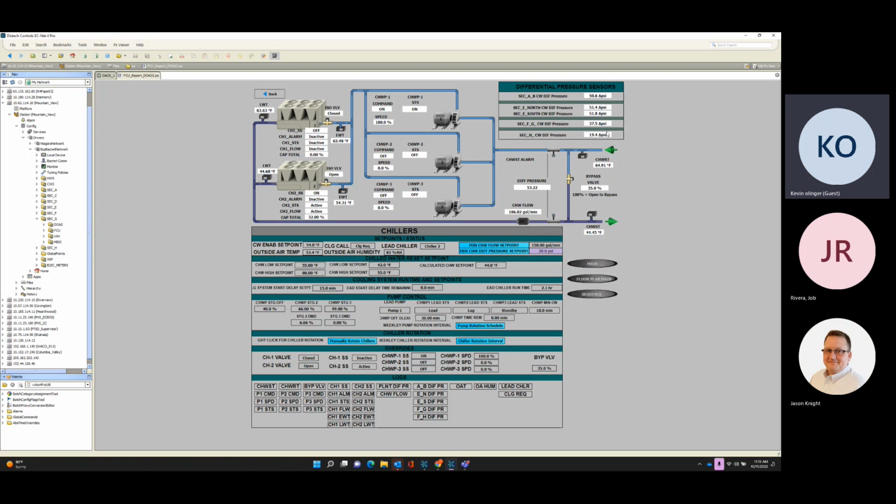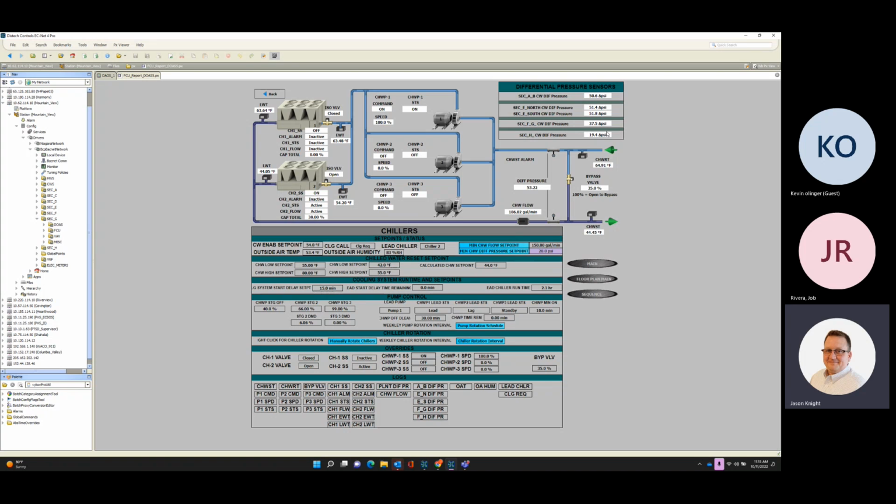Let me paraphrase that, to make sure I'm understanding the right thing. In order to get 20 pounds all the way out at H, it takes 50 pounds at a lot of the other zones that are closer to the pump system. Is that correct? Correct. It's making 50 pounds. So, okay.